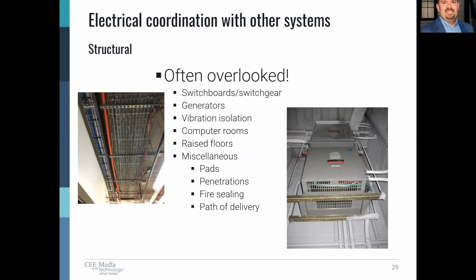But in addition to physically supporting the load, there are also elements of vibration isolation that must be considered. If you think about a research facility, for example, where you have sensitive equipment in a space, it's important that we consider vibration isolation and the effects that, say, a vibrating transformer or a generator in a building are going to have on the equipment that's adjacent to that space. These are all elements that we need to be coordinating early and often during the design process with our structural engineers.